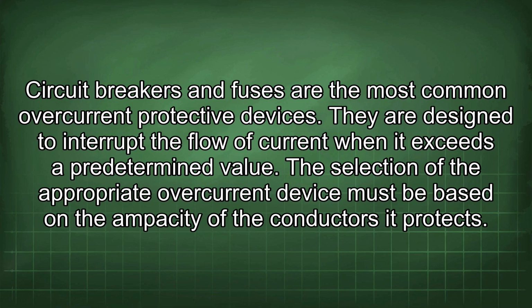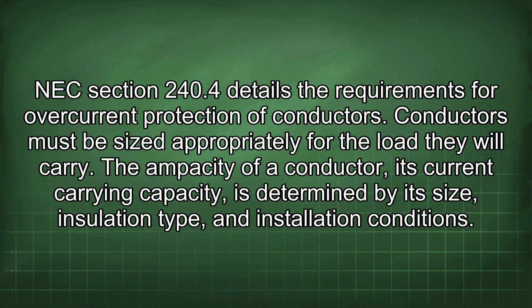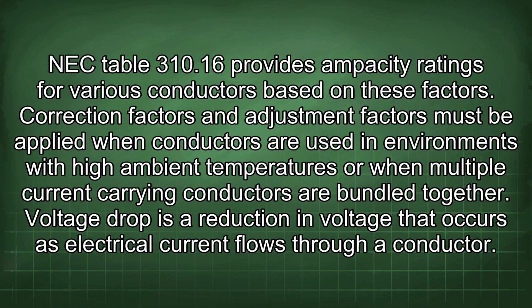The selection of the appropriate overcurrent device must be based on the ampacity of the conductors it protects. NEC Section 240.4 details the requirements for overcurrent protection of conductors. Conductors must be sized appropriately for the load they will carry. The ampacity of a conductor, its current carrying capacity, is determined by its size, insulation type, and installation conditions. NEC Table 310.16 provides ampacity ratings for various conductors based on these factors. Correction factors and adjustment factors must be applied when conductors are used in environments with high ambient temperatures or when multiple current-carrying conductors are bundled together.